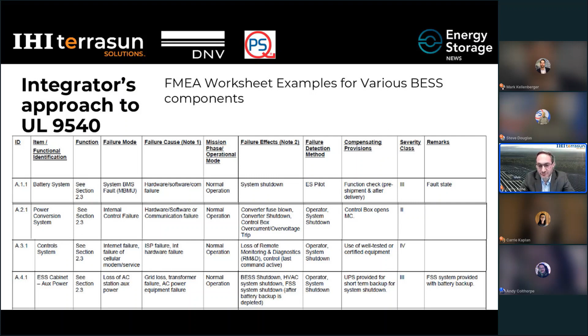Now, we'll talk briefly about changes in the industry that we are all still working through, and about ensuring that new projects meet them. The biggest change recently was in September 2021, when NFPA 855 changed to now require that battery cabinets meet either NFPA 68 or NFPA 69 requirements. NFPA 68 is deflagration venting, and NFPA 69 is explosion prevention. Previously, energy storage cabinets, while maybe they were required to meet these requirements, it was not specifically stated.